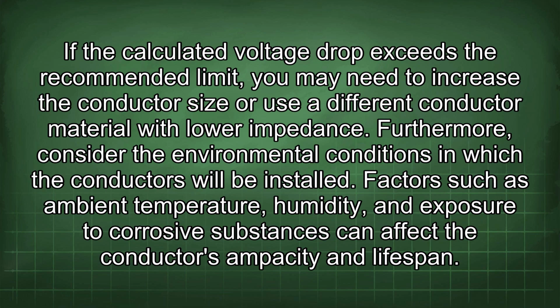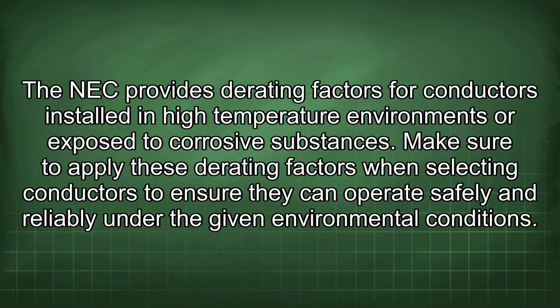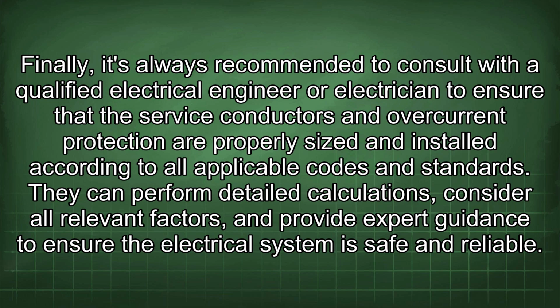Furthermore, consider the environmental conditions in which the conductors will be installed. Factors such as ambient temperature, humidity, and exposure to corrosive substances can affect the conductor's ampacity and lifespan. The NEC provides derating factors for conductors installed in high-temperature environments or exposed to corrosive substances. Make sure to apply these derating factors when selecting conductors to ensure they can operate safely and reliably under the given environmental conditions. Finally, it's always recommended to consult with a qualified electrical engineer or electrician to ensure that the service conductors and overcurrent protection are properly sized and installed according to all applicable codes and standards.